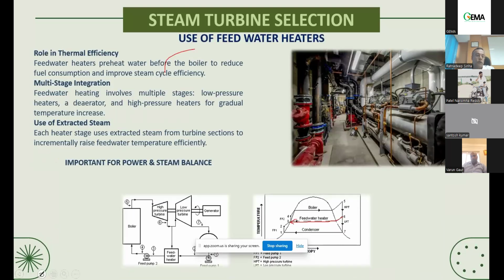So therefore, feed water heating involves multiple stages. There will be low pressure heaters, where obviously we are using the condenser. The deaerator is a direct contact type heater, which will be there anyway, because we have to scavenge oxygen from the system. Also, it acts as a preheater. Basically, it acts as a heater which changes the temperature of the condensate or the DM water to a certain level.